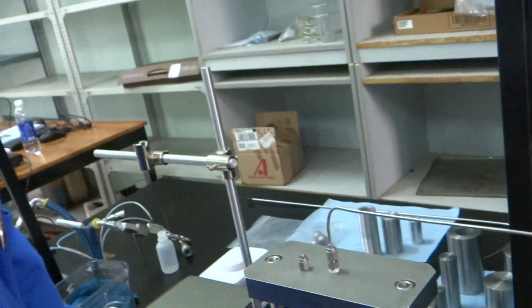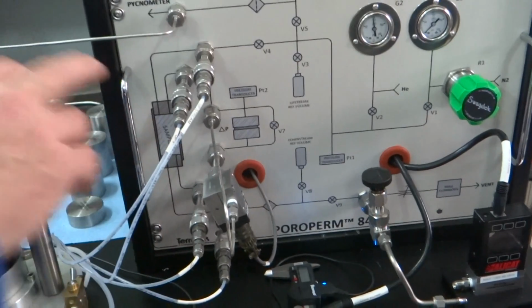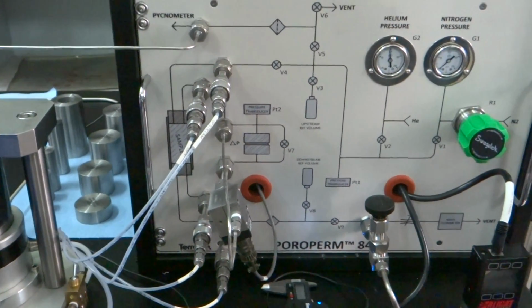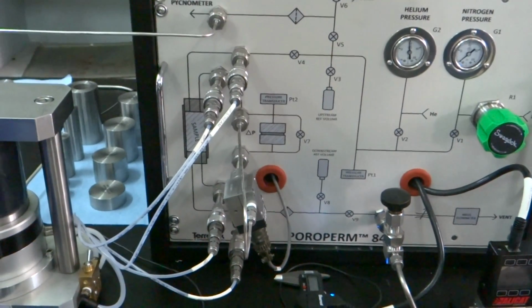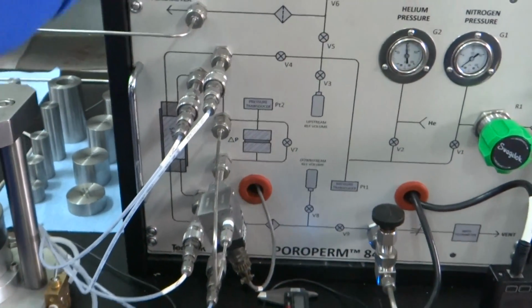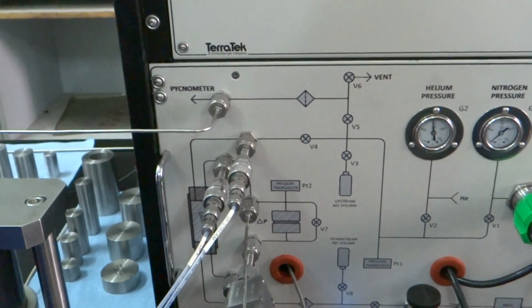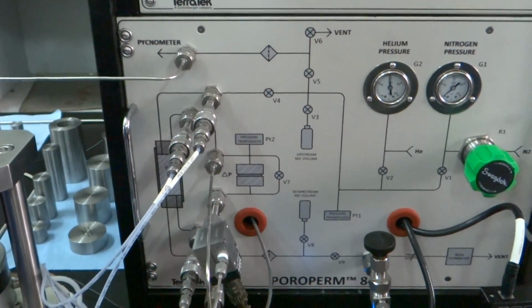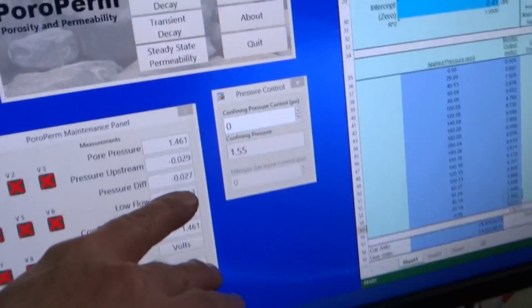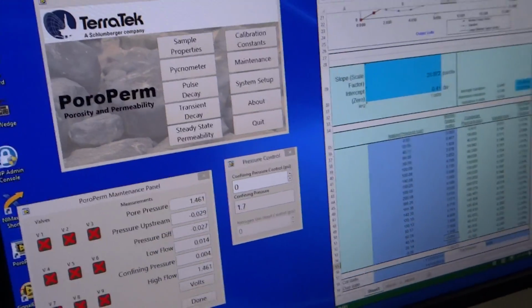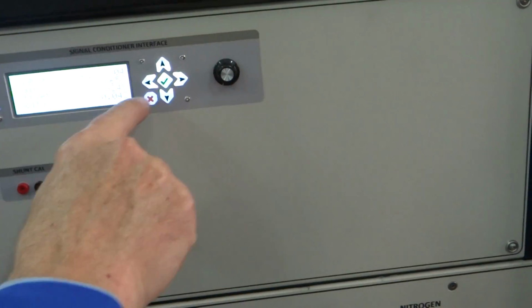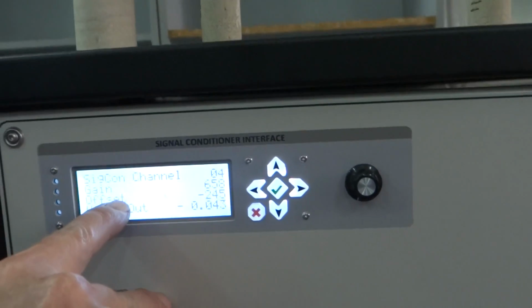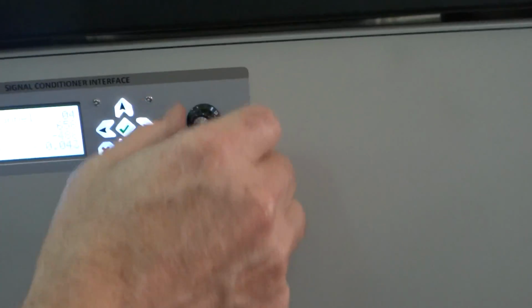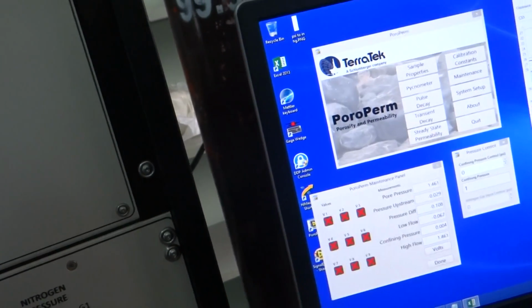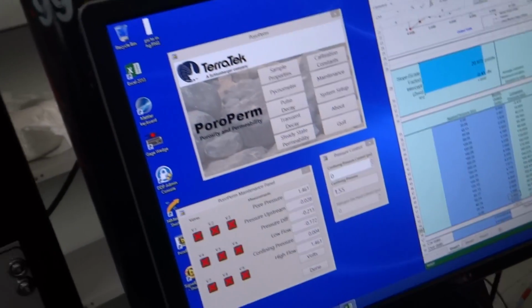What's offset? Offset is, there's an electrical offset in the transducer so it doesn't read 0. Okay. So to get it to read 0 when there's no pressure, you adjust that offset. So right now it's pretty close to 0, but if you get the asterisk on the offset, and then if you adjust here, you can see that the offset is going.